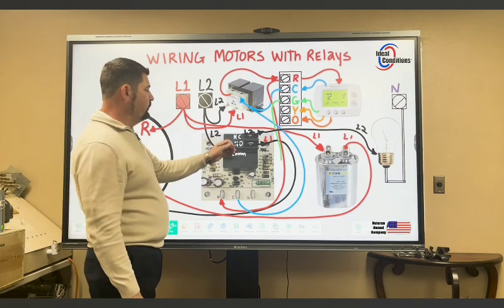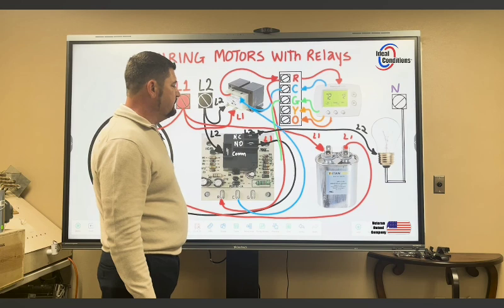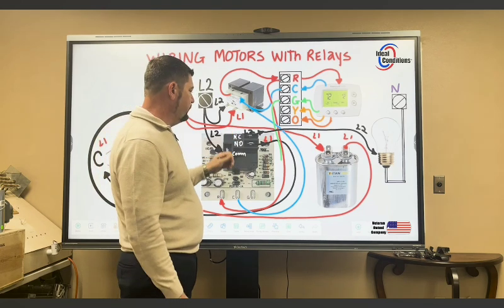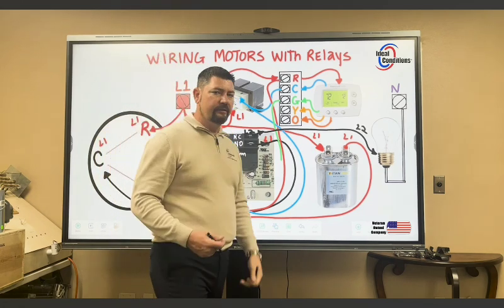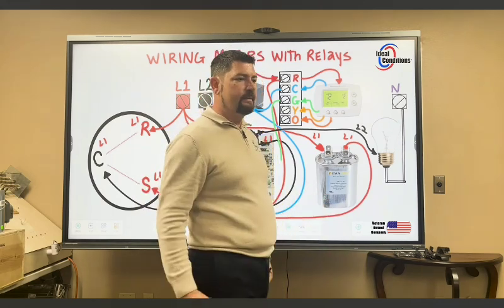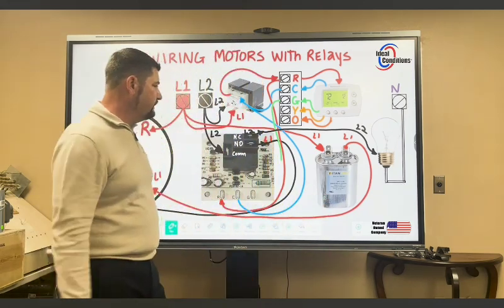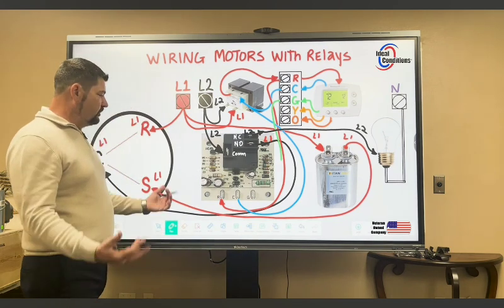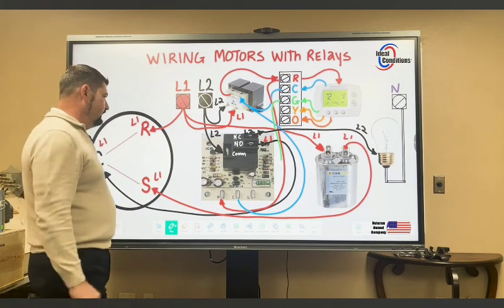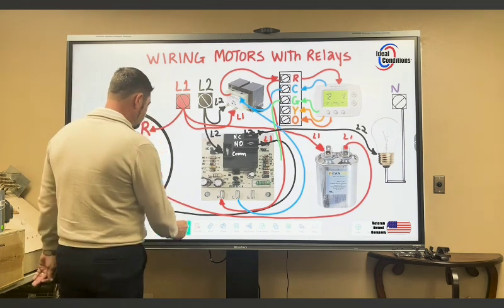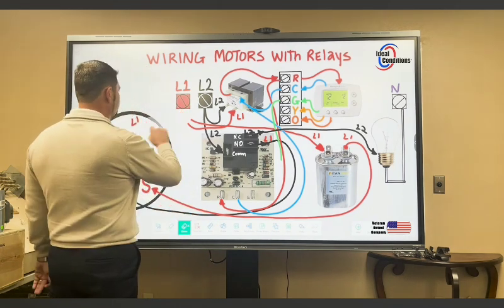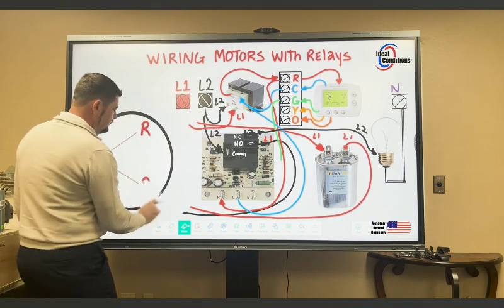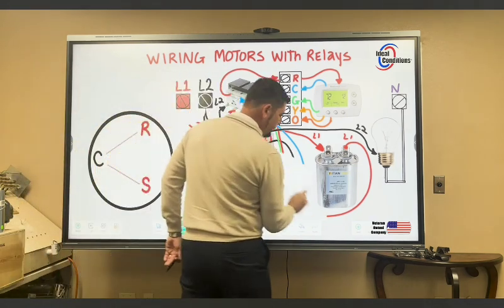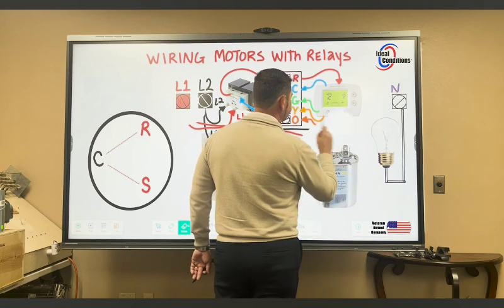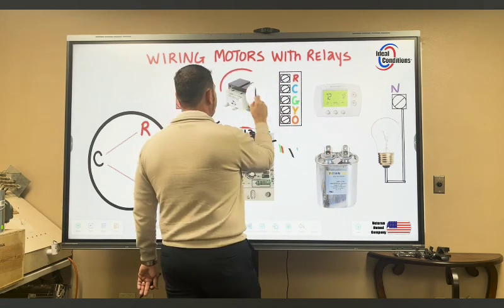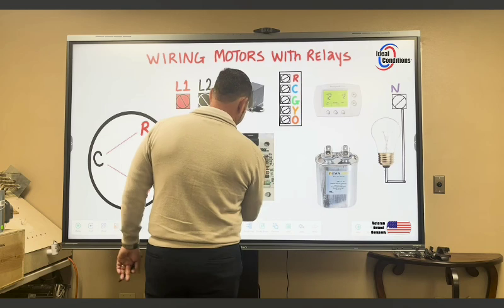I would not wire two speeds here, like a low speed and a high speed, because there is a brief second where power is on both of these terminals for about a second or two. You don't want to energize two motors at the same time. That could hurt your motor, or two windings at the same time can hurt your motor. I'm going to show you how you would traditionally wire this up so I don't leave off on this note. I'm going to go ahead and clean it up and redraw this. It's easy to erase it, especially when we know what we're doing. And we're going to do this again step by step. It's very easy.